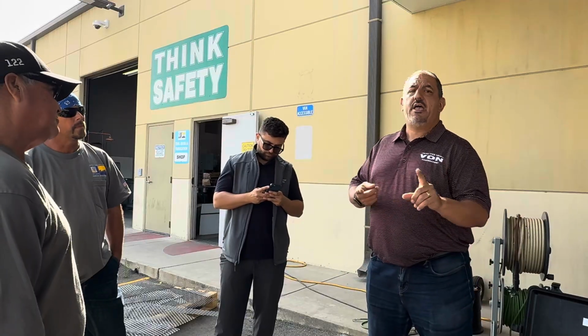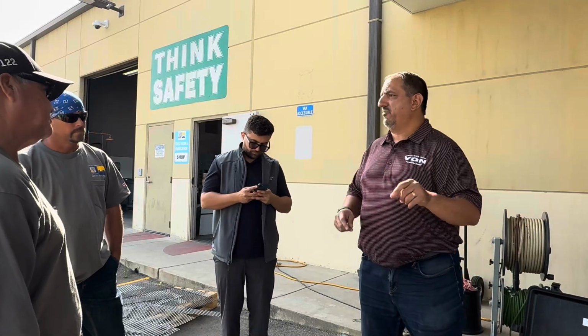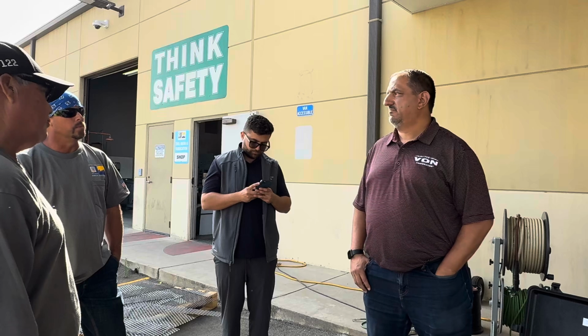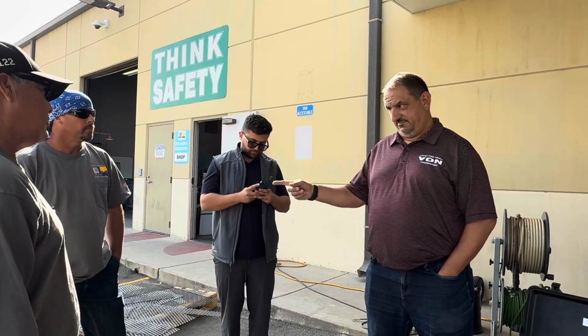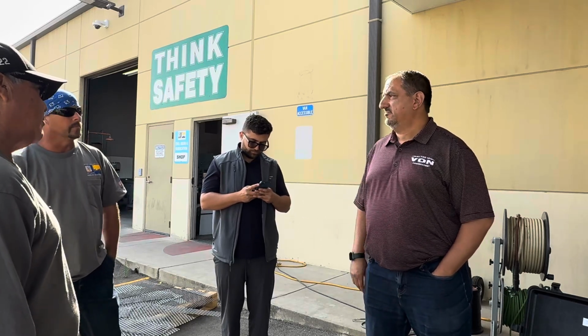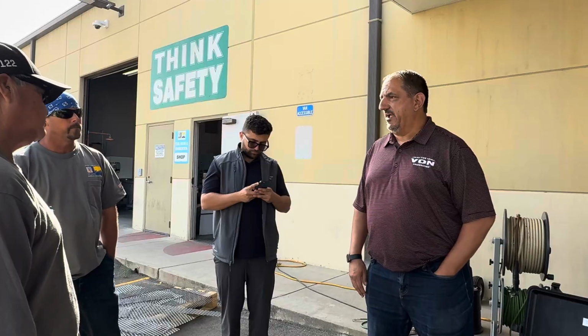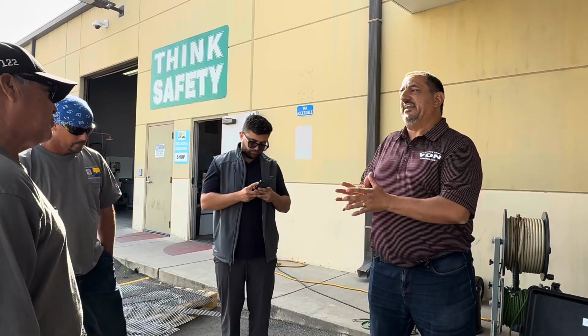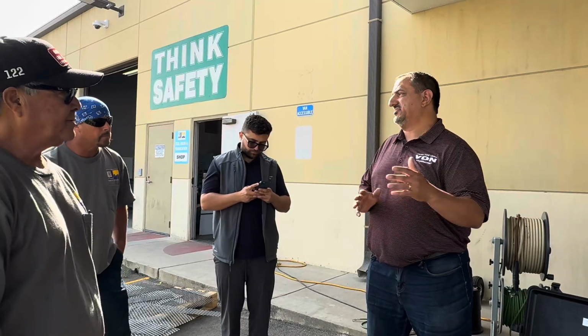It will only show you one fault. Whichever one falls quickest, whichever one goes to ground first, least resistance. More times than not, it's the closer one, but not necessarily.